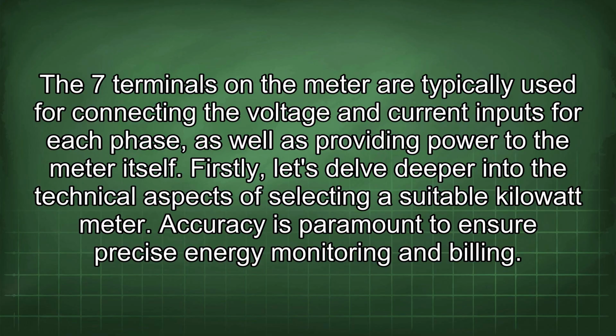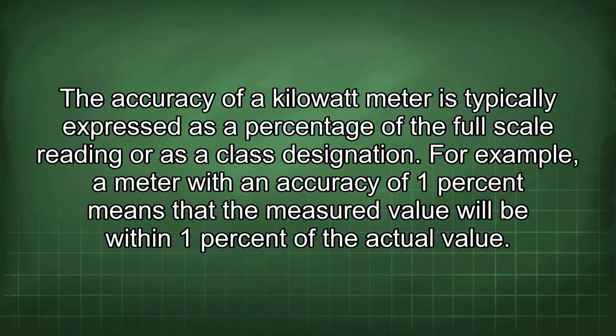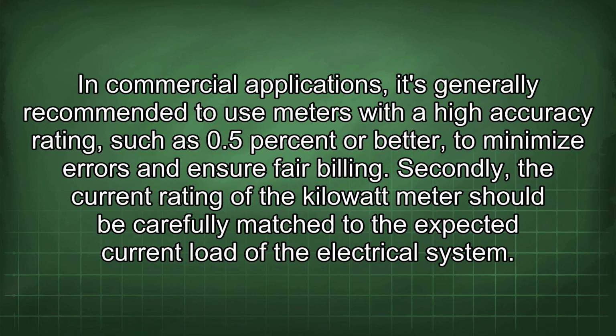Firstly, let's delve deeper into the technical aspects of selecting a suitable kilowatt meter. Accuracy is paramount to ensure precise energy monitoring and billing. The accuracy of a kilowatt meter is typically expressed as a percentage of the full-scale reading or as a class designation. For example, a meter with an accuracy of 1% means that the measured value will be within 1% of the actual value. In commercial applications, it's generally recommended to use meters with a high accuracy rating, such as 0.5% or better, to minimize errors and ensure fair billing.